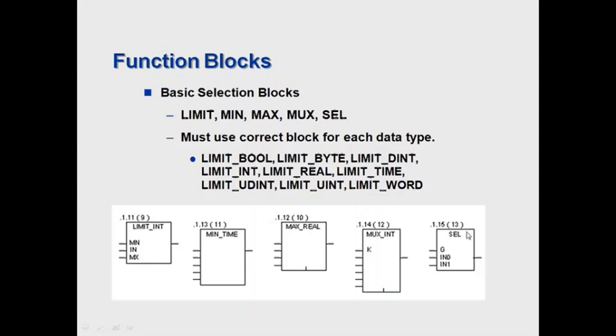The select block is just a digital selection block, similar to the mux or multiplexer. It's only an on or an off. When the G is zero, whatever input zero is will be shown on the output. And when the G is a value of one or true, the input one value will be shown on the output side of this block.